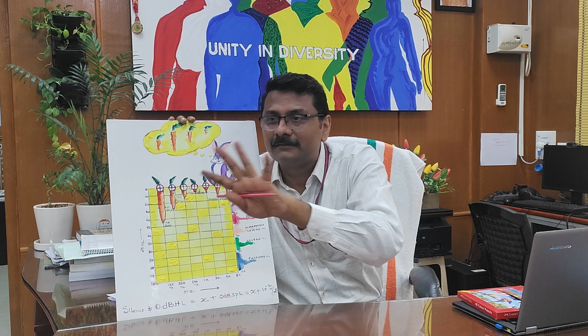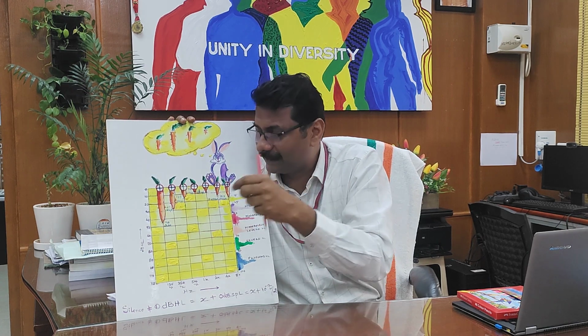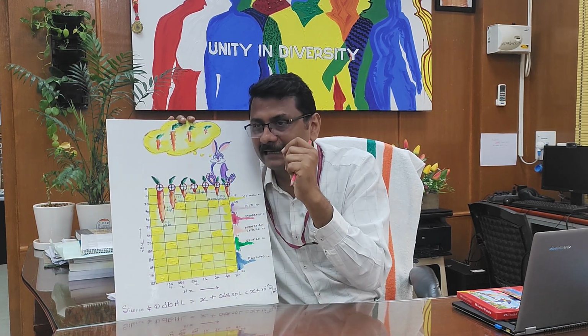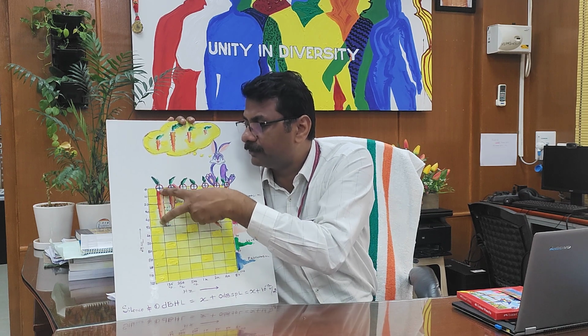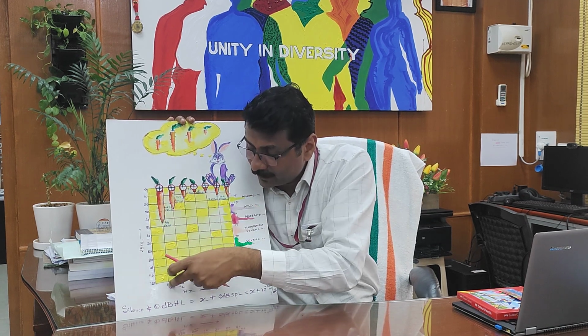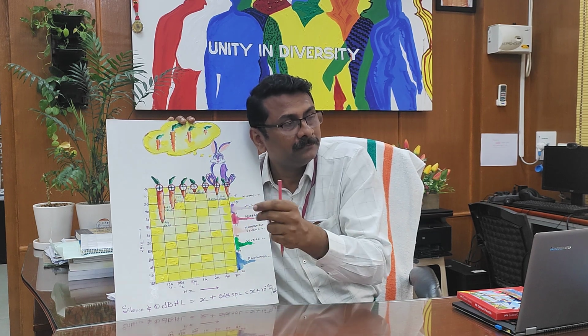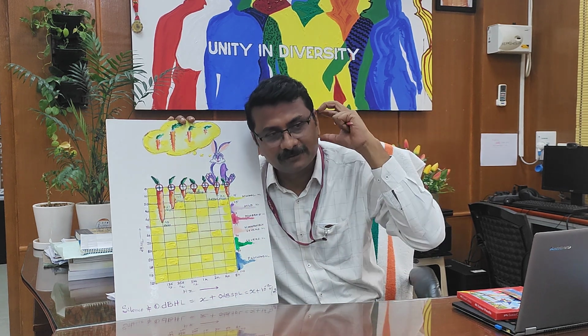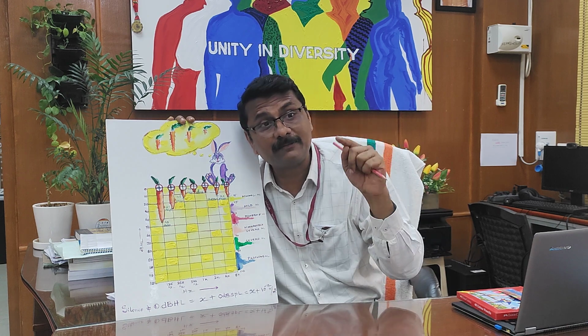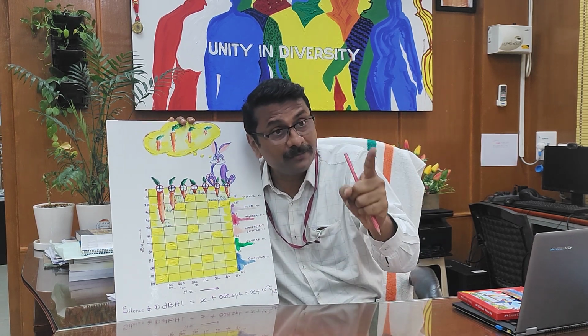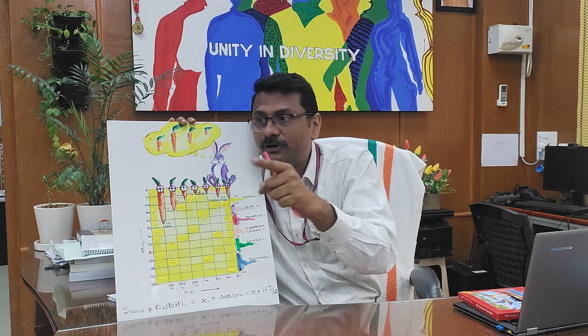So a group of 500 people we have seen. Okay, this is the amount of sound which a person can hear. This is the SPL sound. We put this much of sound at 125 Hertz, 0 dB HL. It will be fed in the audiometer. So the moment you hear it, automatically that amount of sound will be coming at 0. So 0 dB is not silence, understood? So that is the 0 dB HL concept.